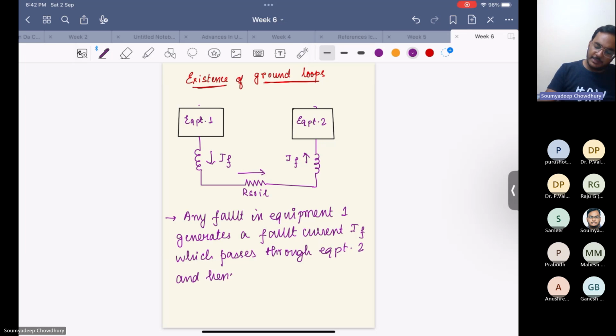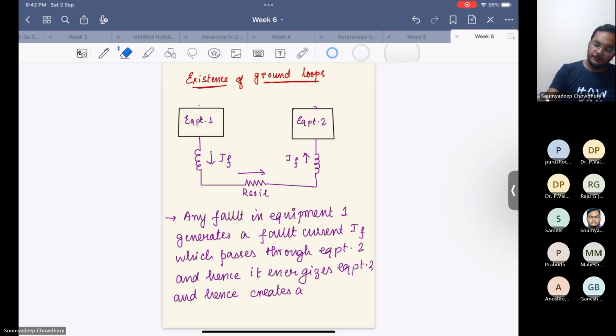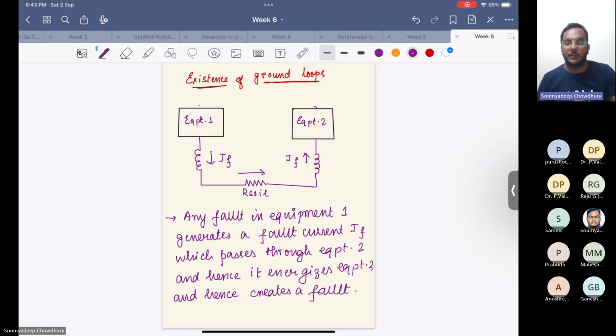And hence it energizes this equipment too, and hence it creates a separate fault. So basically what is happening, any fault in equipment 1 generates a fault current IF, which flows through the soil into equipment 2. This energizes equipment 2 and hence creates another fault. So this is not desirable, right? Because we had designed this grounding, the ground loops, for mitigation of the fault. Rather, another fresh new fault is happening in another equipment, and equipment 1 and equipment 2 can be separated by distances, right? So that is creating another fault.